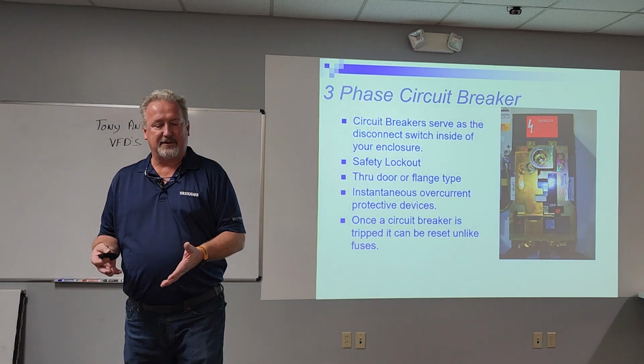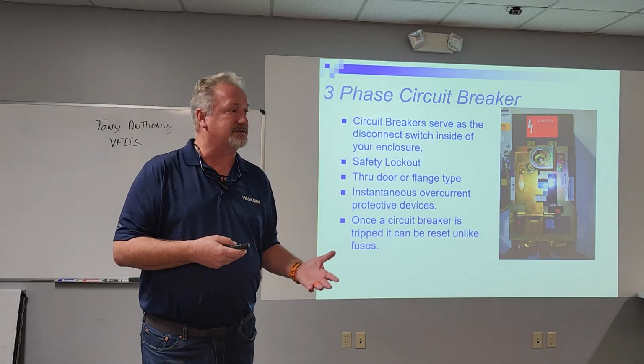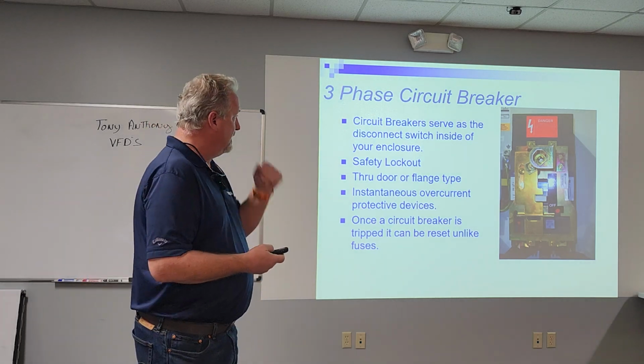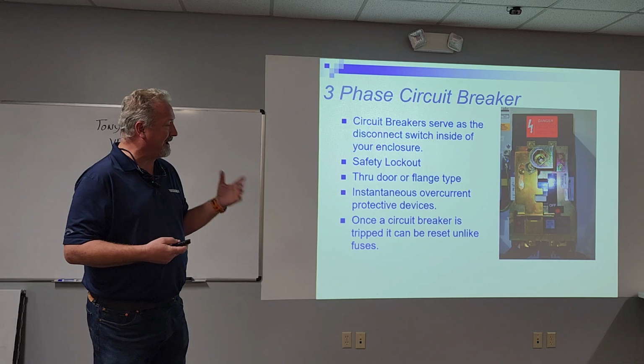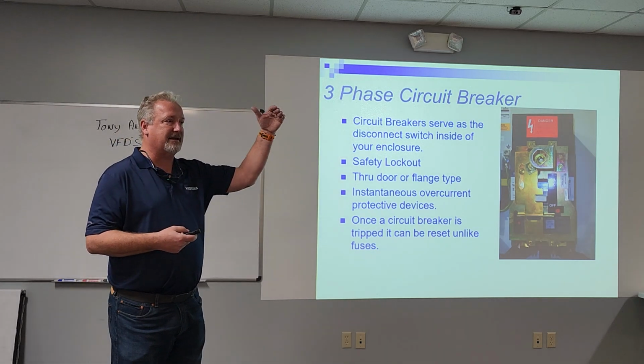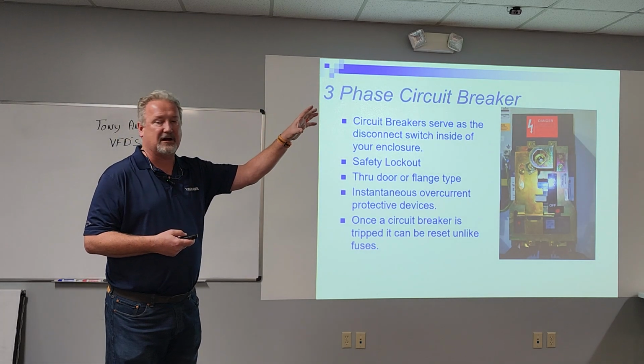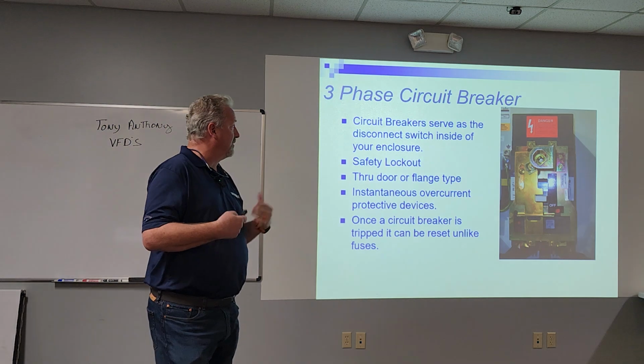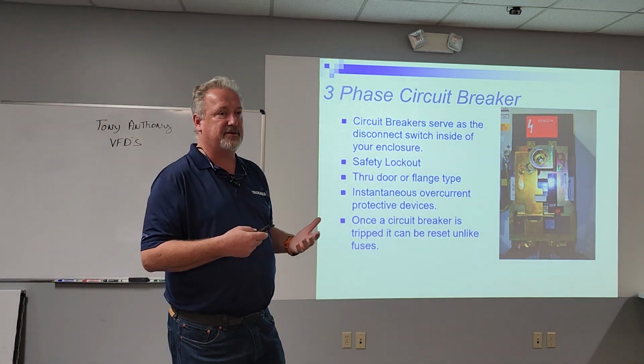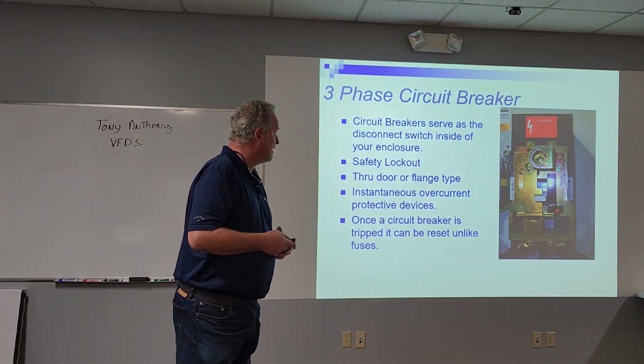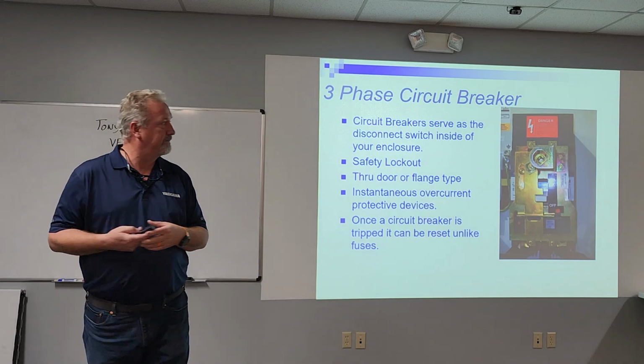Before you have a drive, you've got to have some way of getting the electricity to the drive. So on the input side of the drive, by code, you've got to have a disconnecting means and short circuit protection feeding that drive. It used to always be fuses, but one of the more common things we're seeing now is circuit breakers.